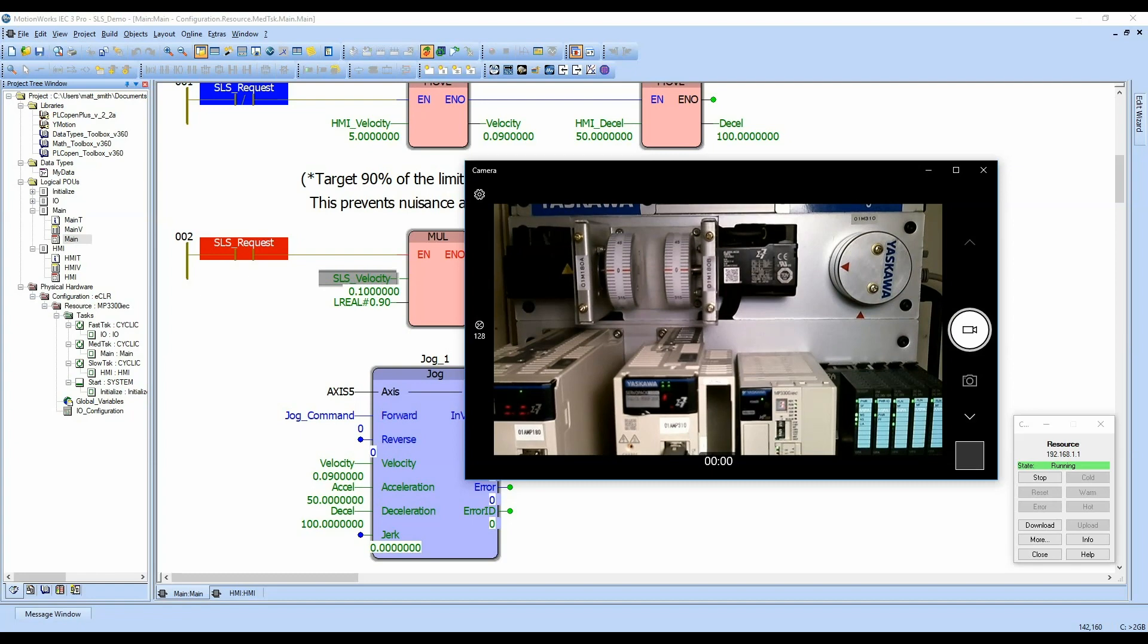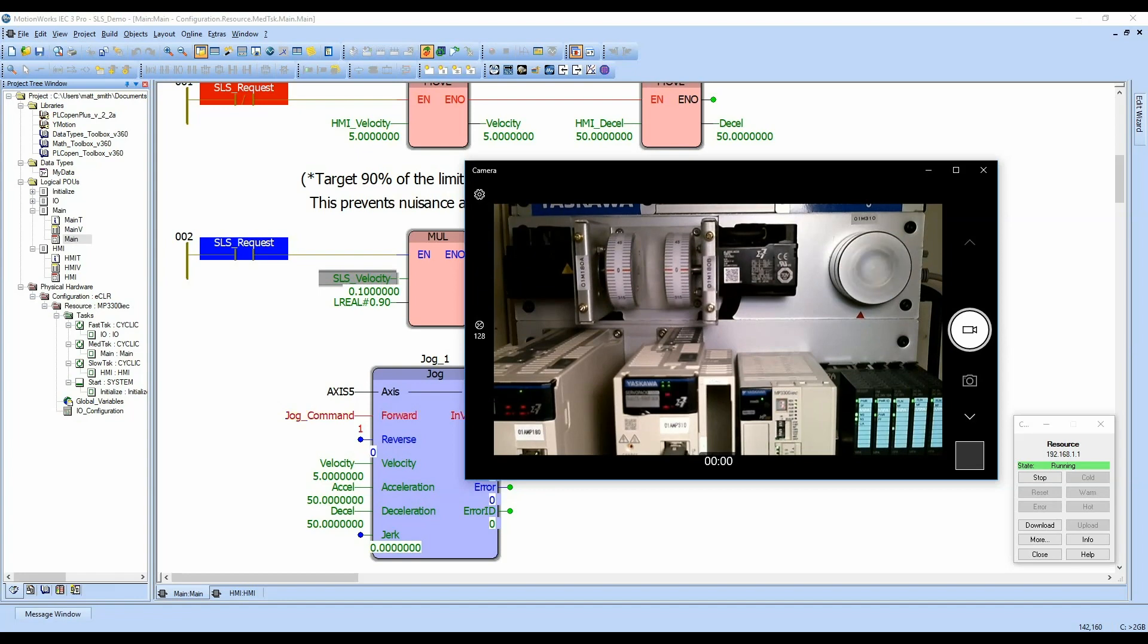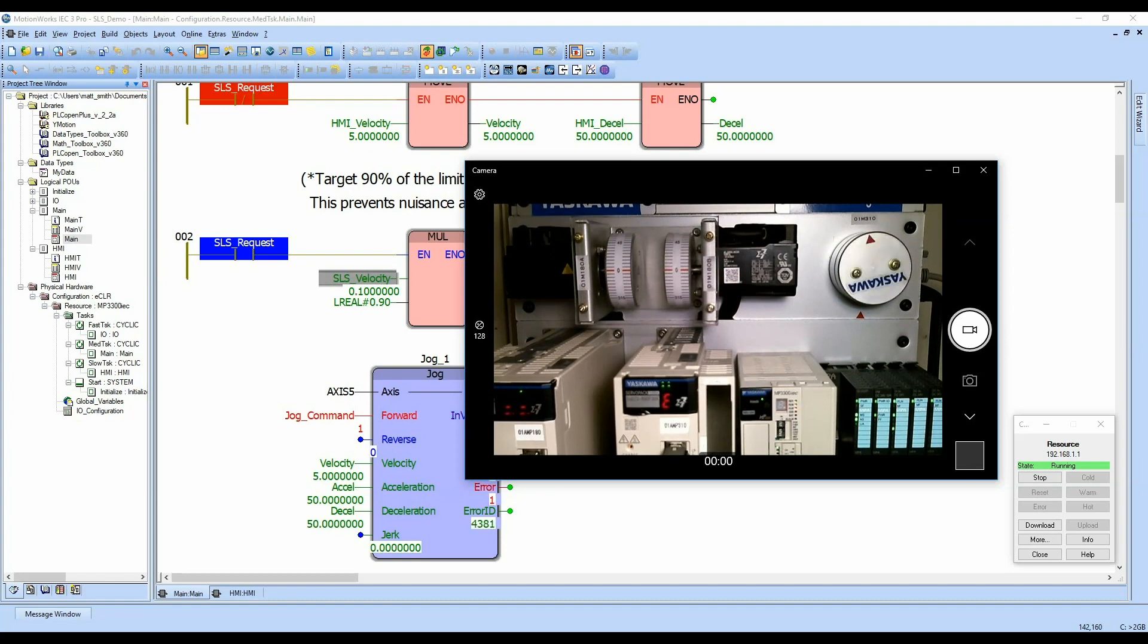What we can do is say maybe the input into the controller is such that it didn't see that it needs to run slower, or maybe someone changed the program and it is no longer going that safe speed. And if we were to clear our safe limited speed input, you can see that the drive has no status on it there. And we're running a lot faster. In this case, we're not going to actually command the motor to slow down. We're just going to activate the safe limited speed. Once we do that, we see our timer and then our time is elapsed and we're still exceeding the velocity. So then the drive creates an alarm and disables the servo motor. And then we have diagnostic on the drive saying that the safe limited speed has been exceeded and I've disabled the axis.